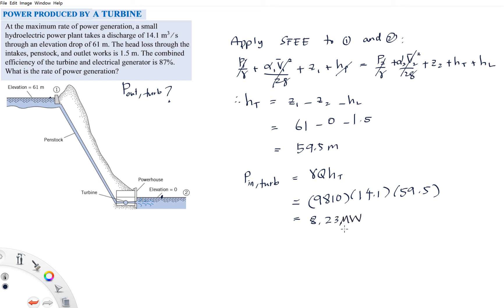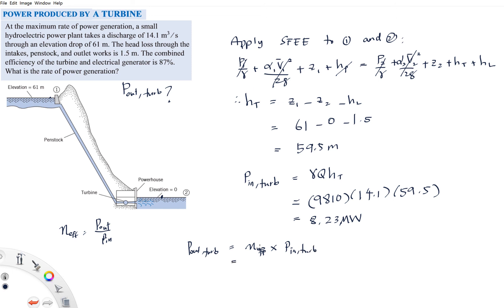To get the power out of the turbine (power generated), we apply the combined efficiency of 87%. Efficiency = p_out / p_in, so p_out = efficiency × p_in = 0.87 × 8.23 MW, giving a final answer of approximately 7.16 megawatts.